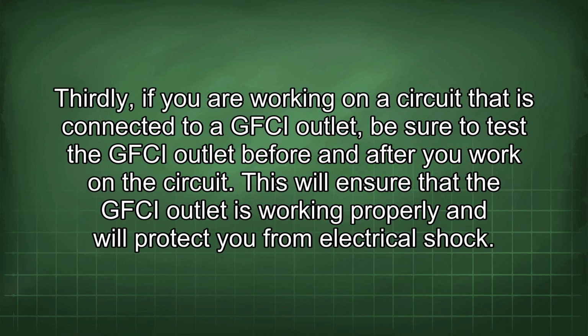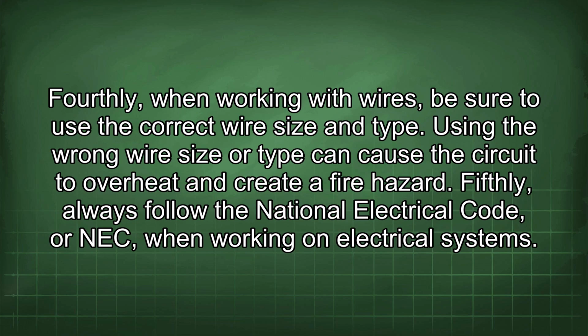Thirdly, if you are working on a circuit that is connected to a GFCI outlet, be sure to test the GFCI outlet before and after you work on the circuit. This will ensure that the GFCI outlet is working properly and will protect you from electrical shock. Fourthly, when working with wires, be sure to use the correct wire size and type. Using the wrong wire size or type can cause the circuit to overheat and create a fire hazard.